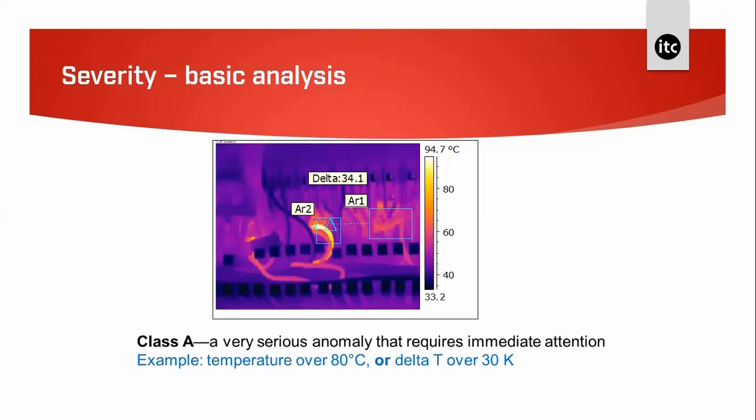This image shows a delta T of 17.7°C — again a Class B problem. The last image is a Class A problem with a delta T of 34.1°C. From these examples we can see how simple it is to classify the fault found, which in turn helps in reporting the problem and working out a repair strategy.